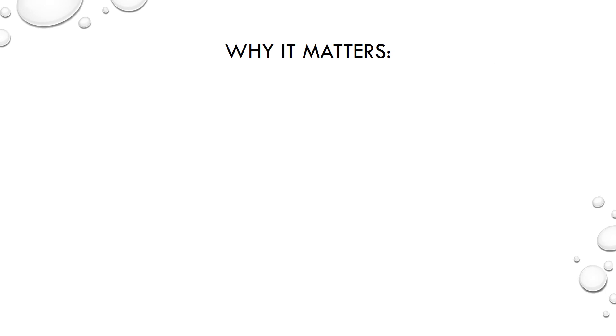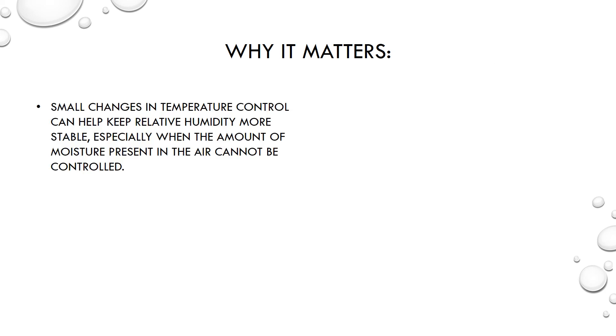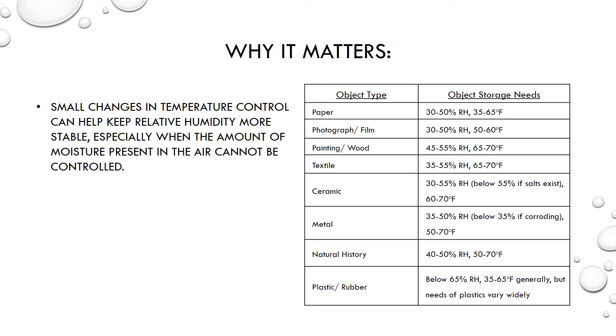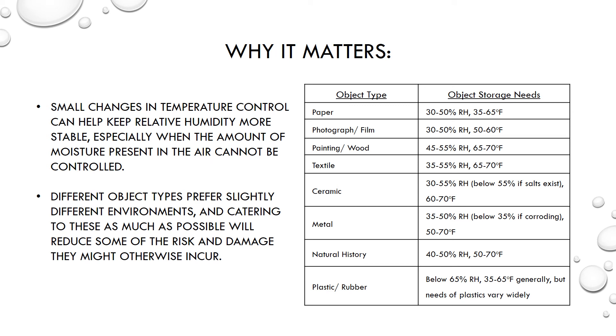Knowing how temperature can affect relative humidity matters. When the amount of moisture cannot be controlled, small temperature changes can keep relative humidity somewhat more stable. Those changes could be the difference that keep humidity from going above 50 or 60 percent in the summer, or from going below 30 or even 20 percent in the winter. This chart demonstrates that different object types have different preferences for their environment, and catering to these as much as possible can help reduce risk and damage. Being within these ranges for as long as possible would help keep these objects around for as long as possible.